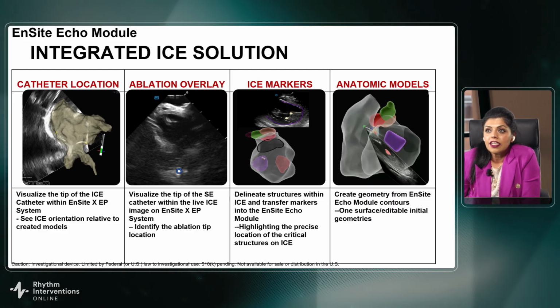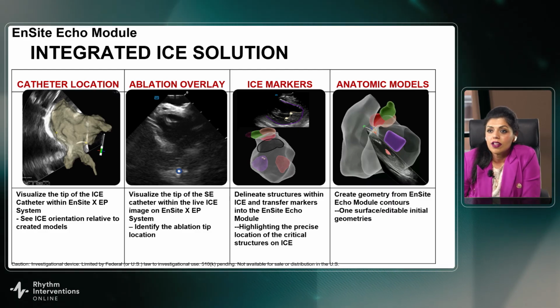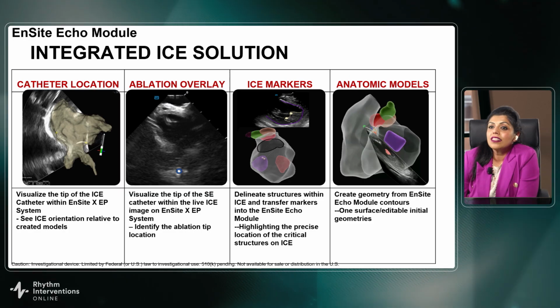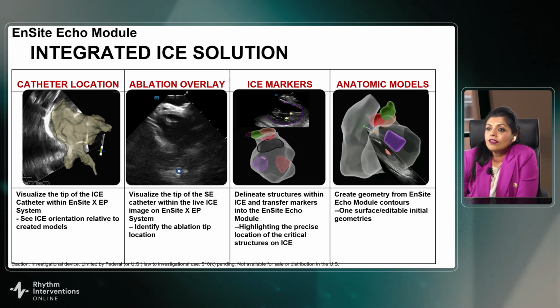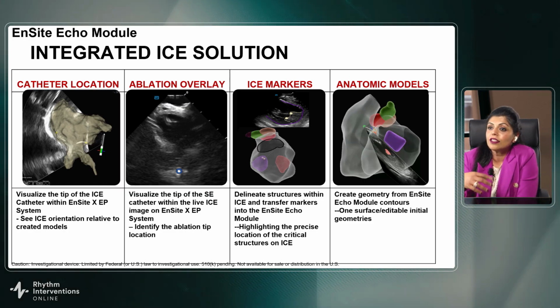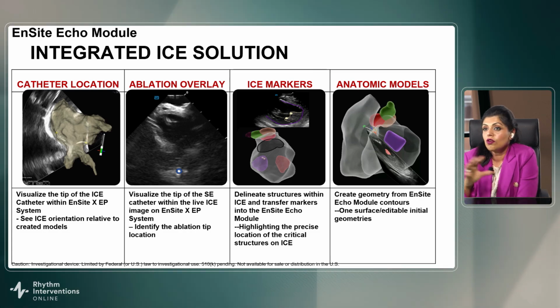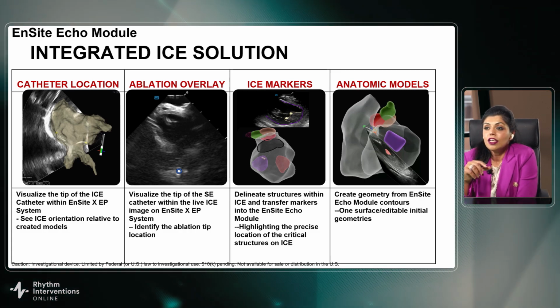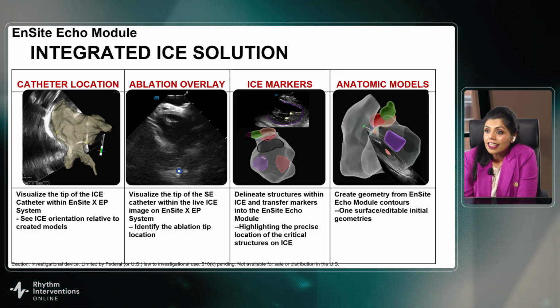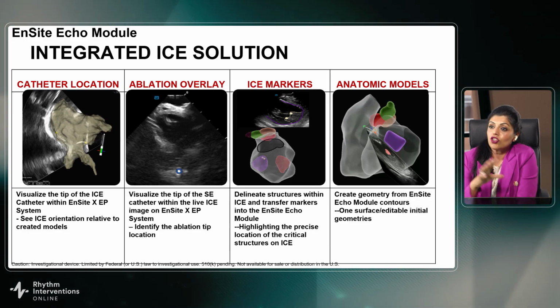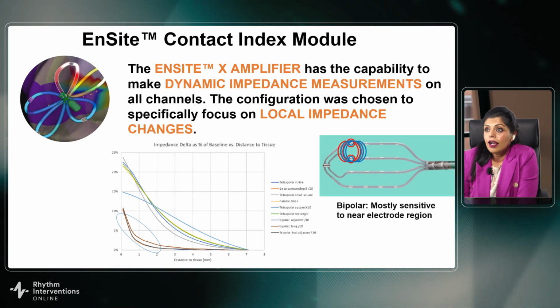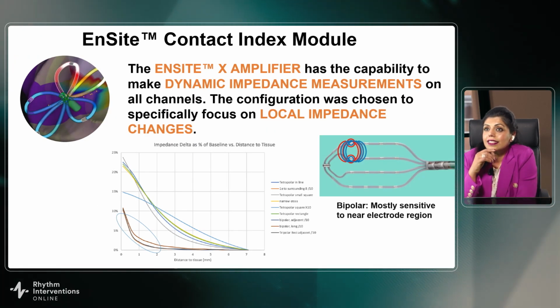The beauty of an integrated ICE solution is that you can visualize the tip of the ICE catheter within the NavX system. You can visualize the tip of the ablation catheter within the live ICE image. So you have both-way connection. You can have ICE markers, so you can delineate these structures within ICE and transfer those markers onto the NavX module. And then there are built-in auto contours with the NavX system.